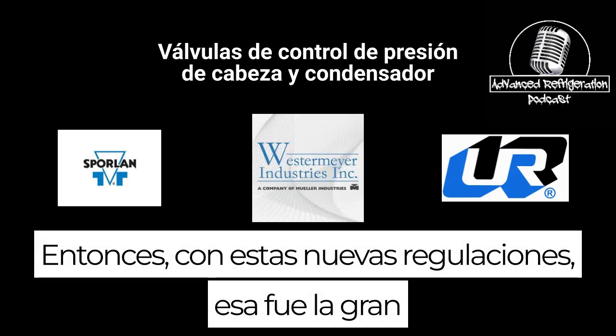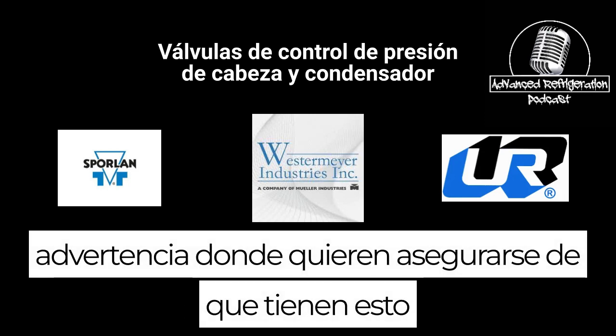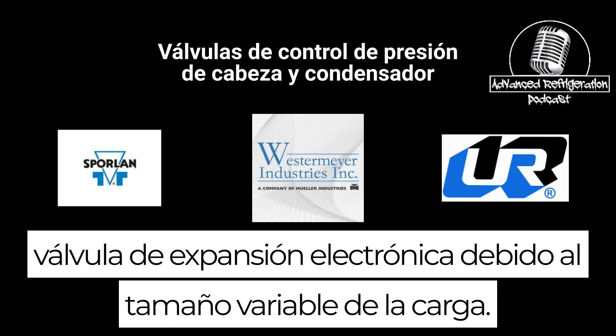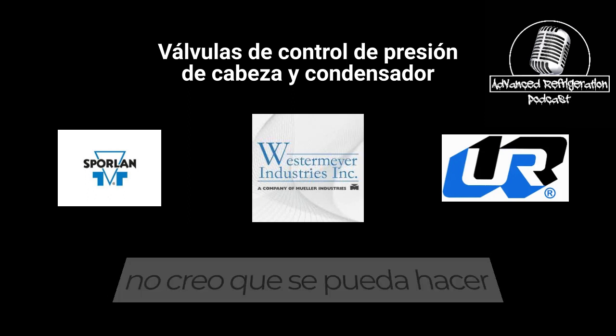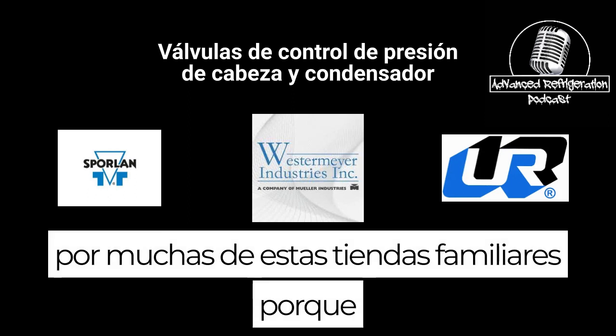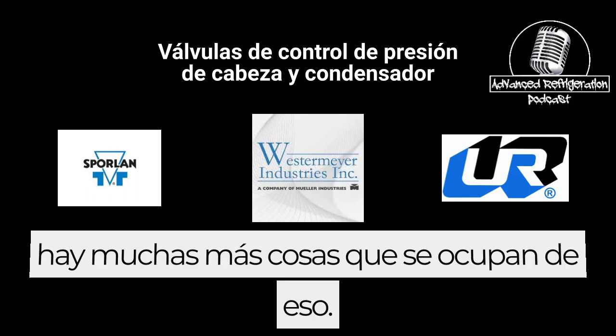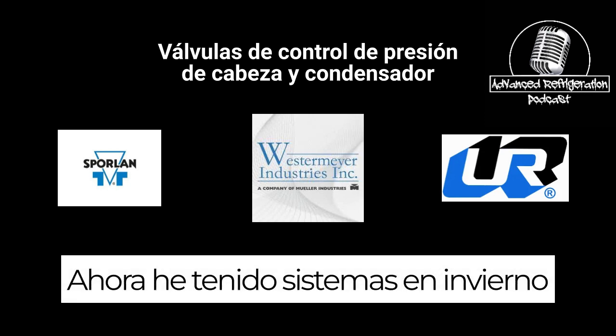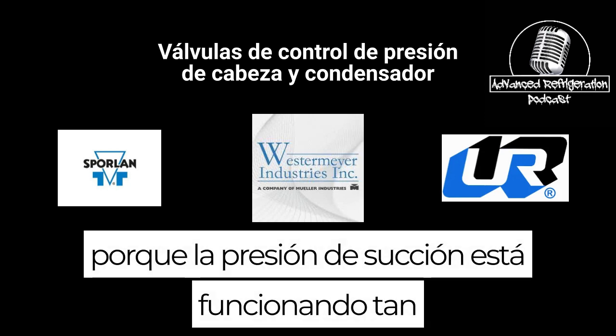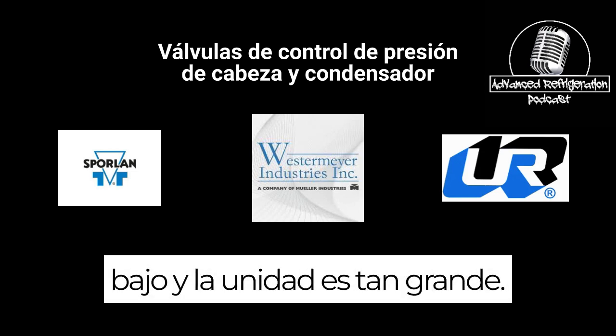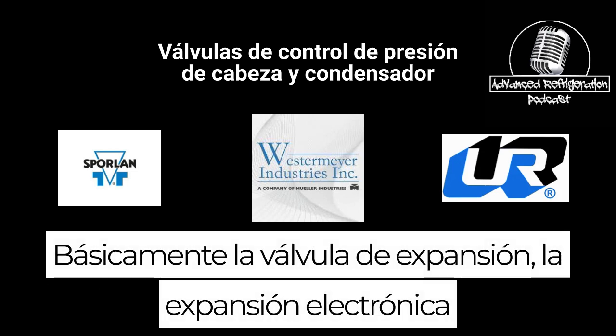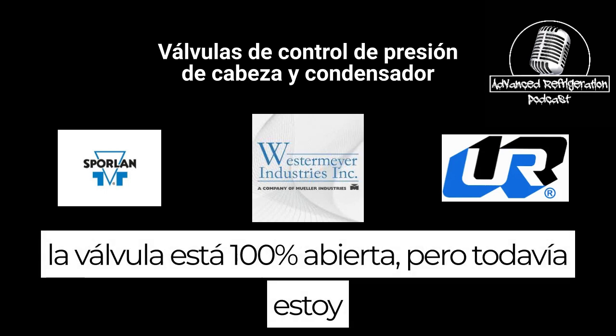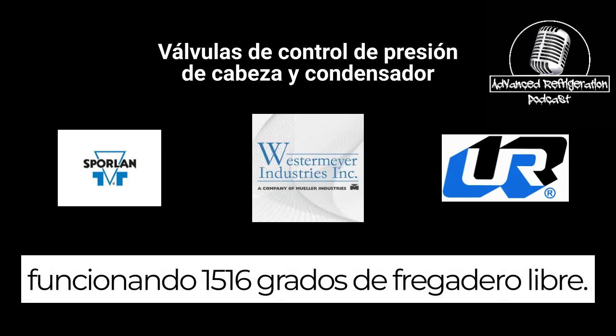So with these new regulations, that was the one big caveat where they want to make sure they have this electronic expansion valve because of the varying load sizing. I don't think it's going to be able to be done by a lot of these mom and pop shops anymore, because there's a lot more that has to be dealt with now. I've had systems in the wintertime where the suction pressure is running so low and the unit's so oversized that the electronic expansion valve is 100% open, but I'm still running 15, 16 degrees of superheat. And it was all because the compressor was oversized.